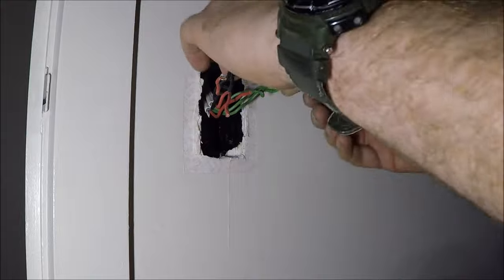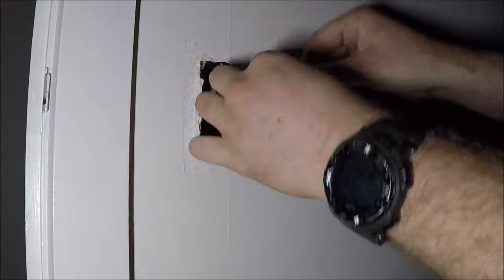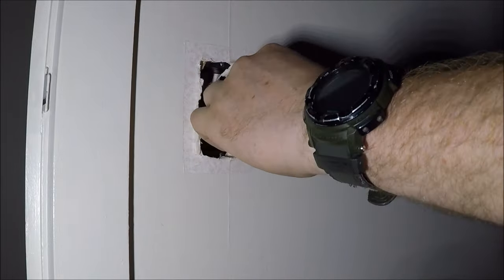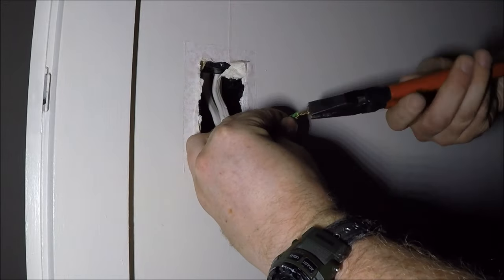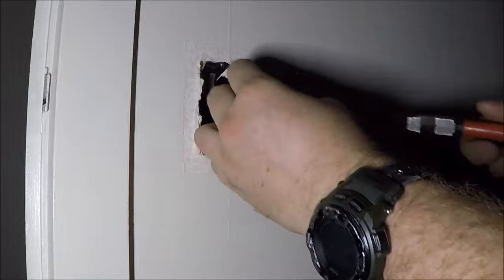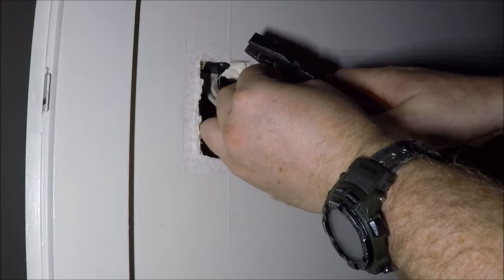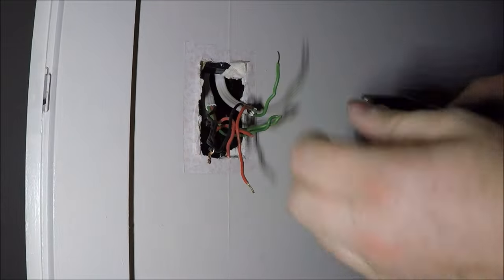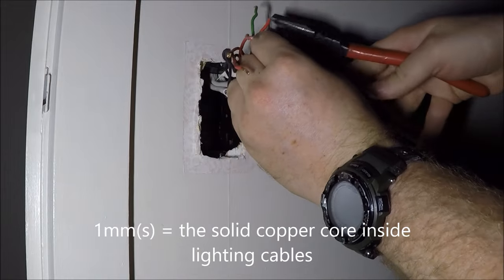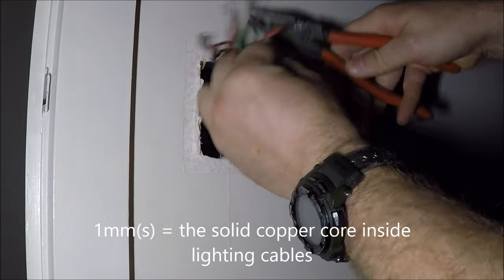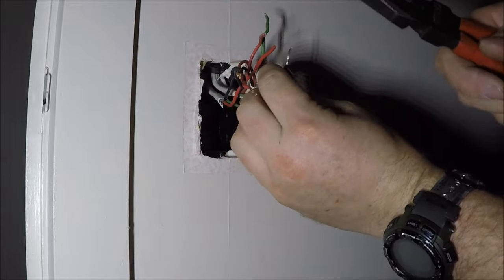So the next part is we check all these terminations and just make sure that the cores aren't snapping like these earths. If I try and twist them up, they'll most likely break like that. So what we want to do, cut the whole lot off, straighten them out, strip them off and re-terminate them. Pretty crucial with these one mills. Every time you play around with them, they'll tend to snap.